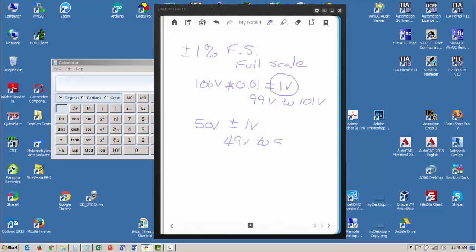to 51 volts and the meter is still in tolerance. That is a lot worse just in the way that the specification was written. When you get a specification of full scale, your readings at mid-scale or lower are going to be bad—or not bad, but they're going to be much less accurate. Let's see what the percent is.